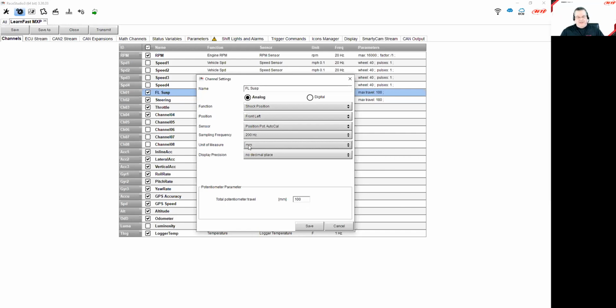That one is linked to this one, and they're very important because of the auto calibration. It needs to know where it's at in its stroke. Then the display precision, no decimal place - that's probably not what I would want. I'd probably want 1 decimal place, something like that. Pick your choice, do what works for you. I'm going to pick 1. And there we go, now I scan over this and everything is fine.